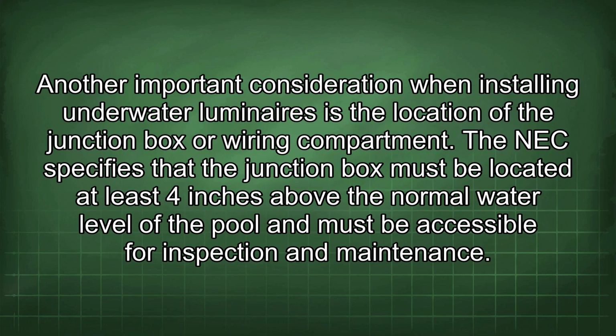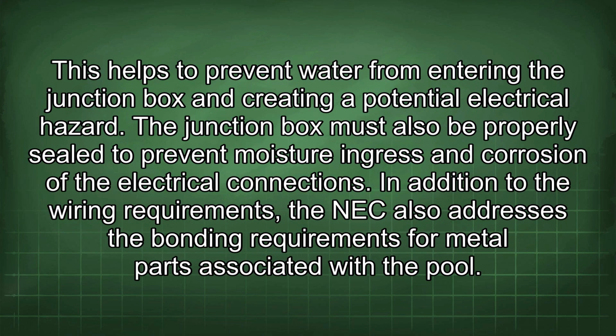Another important consideration when installing underwater luminaires is the location of the junction box or wiring compartment. The NEC specifies that the junction box must be located at least 4 inches above the normal water level of the pool and must be accessible for inspection and maintenance. This helps to prevent water from entering the junction box and creating a potential electrical hazard. The junction box must also be properly sealed to prevent moisture ingress and corrosion of the electrical connections.